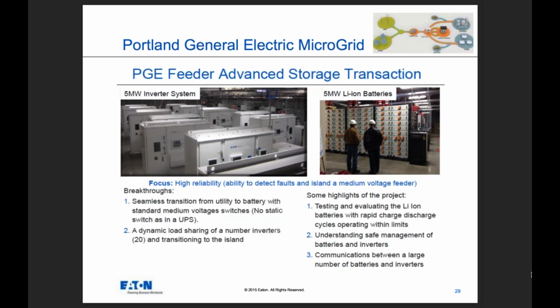That's one area though - battery companies will give you the discharge data, how many charges and discharges you can get at a full discharge. But in a lot of these situations, you're not doing a full discharge and charge, maybe a 20% discharge or a 5% discharge. So the question is, what's the life of that battery at 20% charges and discharges versus 100%? They have very detailed testing on full discharges - they'll tell you can do this 5,000 times. But what if you're only doing a 20% discharge? Do I get 7,000, or does only doing a 20% discharge limit me to 3,000? There's still lots of questions, but a lot of good work is being done on the battery side. There are different battery technologies better suited for short discharges versus larger anticipated discharges.